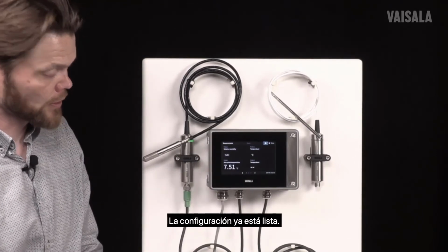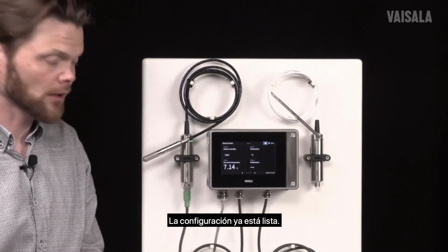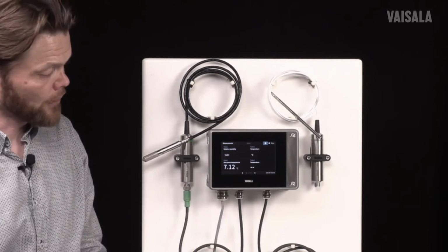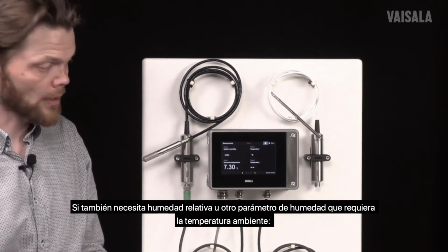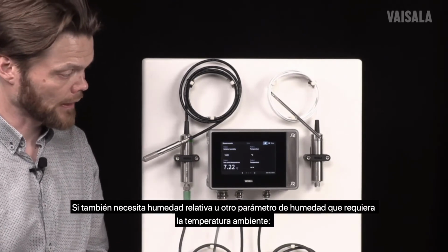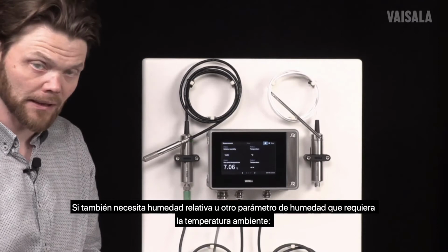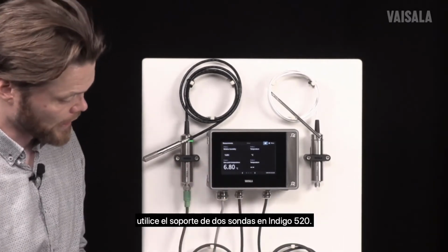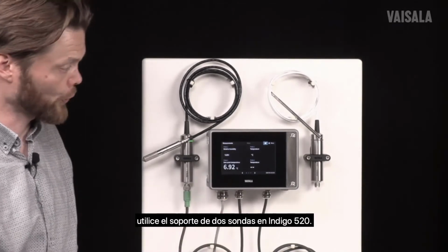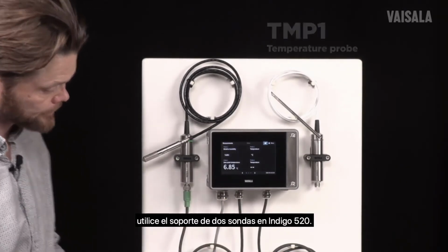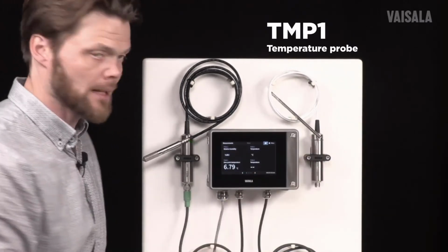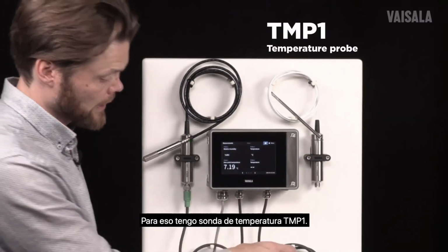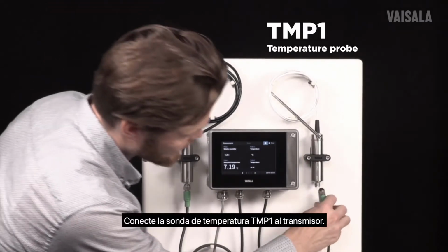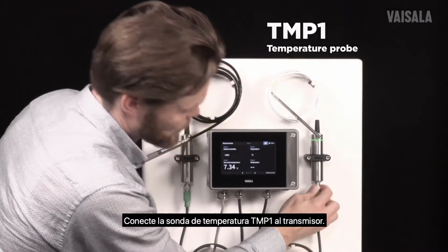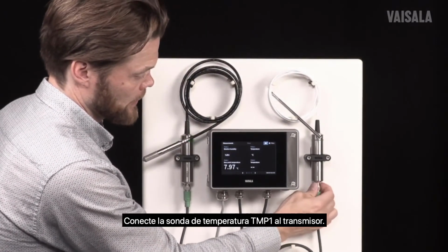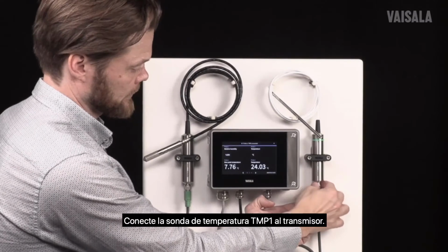If this dew point temperature is what you want to measure, this setup is completely fine. But now if you also need relative humidity or some other humidity parameter that needs the ambient temperature, we can use this functionality of two probe support that this Indigo 520 has. And for that I have TMP1 temperature probe, and let's connect that temperature probe to the transmitter like that.